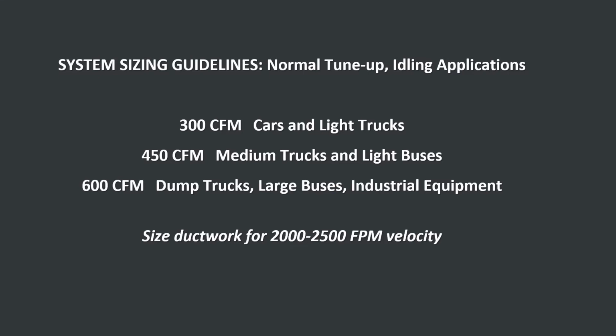And we get this information through the Industrial Ventilation Guidebook. We use those rules kind of as our guide for system design. And the 2,000 to 2,500 feet per minute conveying velocity will allow us to capture the exhaust and its particulate and keep it in our airstream until we deposit it where we want it deposited, as opposed to the particulate falling out in the ductwork along the way.